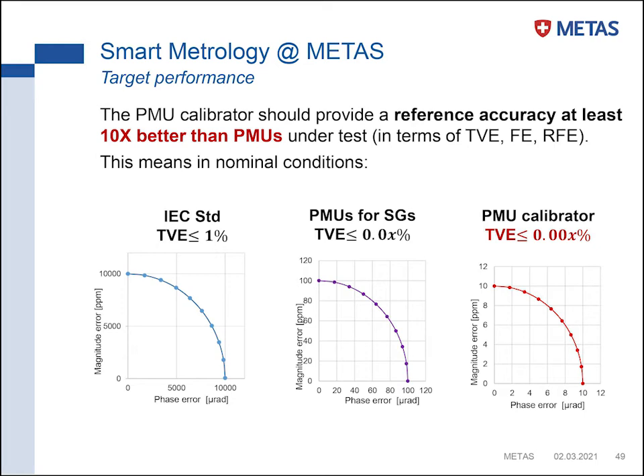The problem is that in the last years, they started to deploy more and more accurate PMUs because they are designed to cope with very challenging conditions. In nominal conditions, so at 50 hertz in a very stable grid, they are able to guarantee a TVE that is 2 orders of magnitude lower than the standard. And so our calibrator should be even 3 orders of magnitude lower. So we would like to be able to guarantee a magnitude error not larger than 10 ppm.